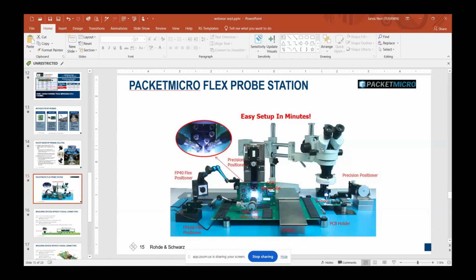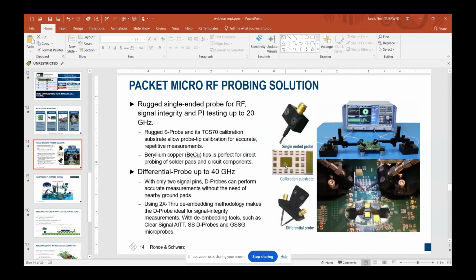You might have a manual microscope. You might have a Dino-Lite microscope, things like that. Those are all possible, and the process is really very similar. You can either calibrate to the end of the probe tips using a calibration substrate, which might have a short, open, load kind of thing. There are other means of calibration. Or you might calibrate to the coaxial interface, and then you have an S-parameter file for the probes, whereby you de-embed it. And where we have a differential probe that doesn't have a ground plane on it, we're probably going to have to de-embed it.